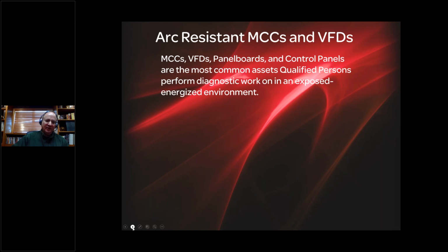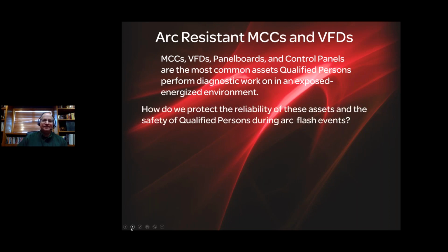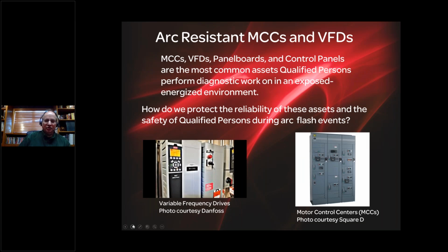So the arc quencher in many cases is installed above these assets. And once you've made that investment in the arc quencher, extending these arc resistant benefits to downstream drives, motor control centers, control panels, and panel boards is relatively inexpensive. By relatively inexpensive, what I mean is the installation labor to extend the sensors and 18-gauge Belden wires to these devices is frequently less than the cost of the equipment. So it's a very economical solution once you've made the initial investment in an arc quencher to extend those benefits to these mission critical downstream assets.